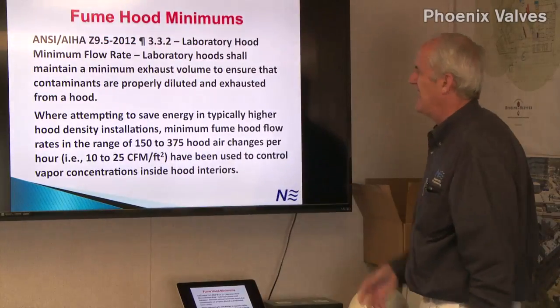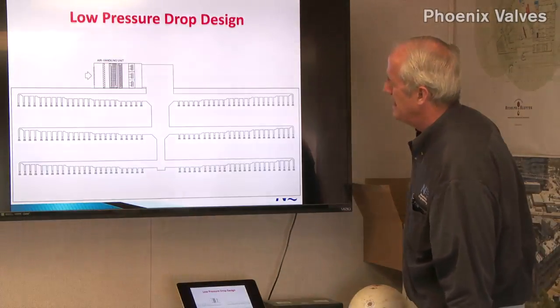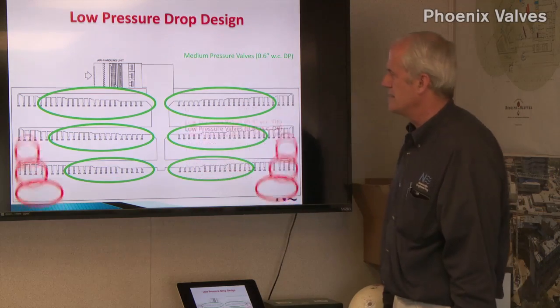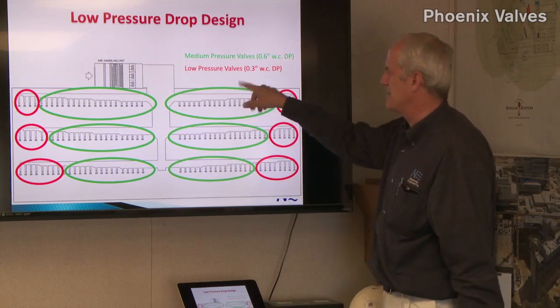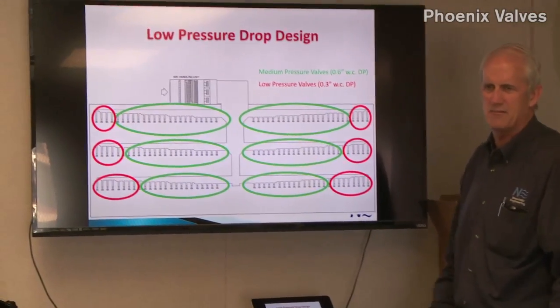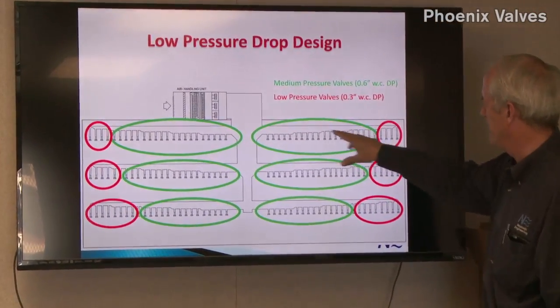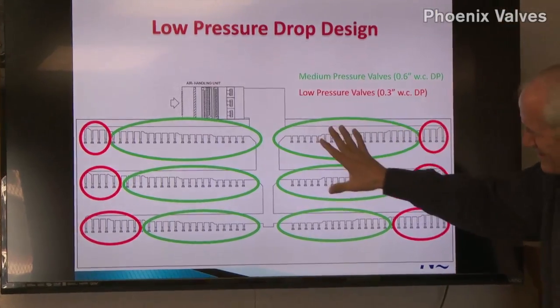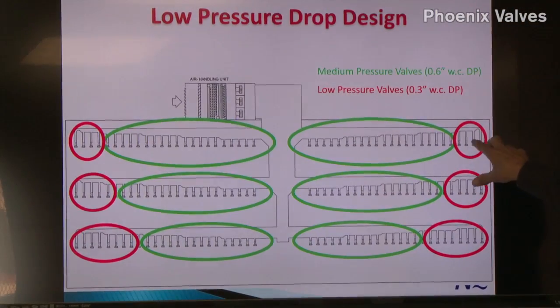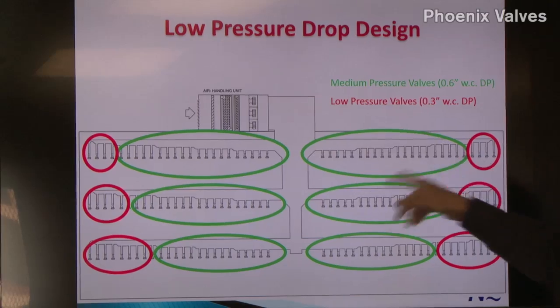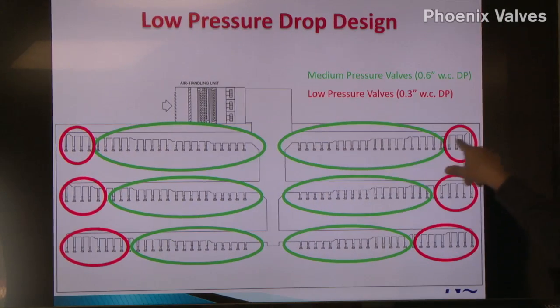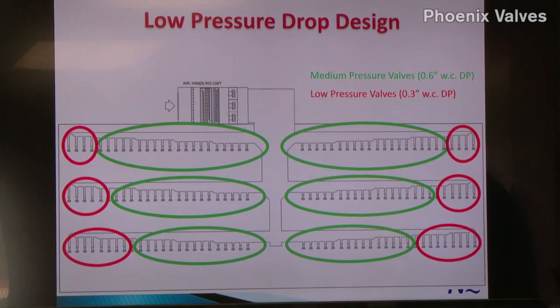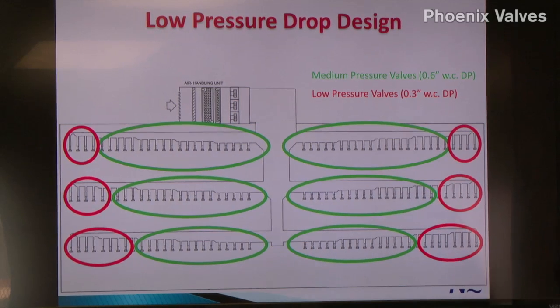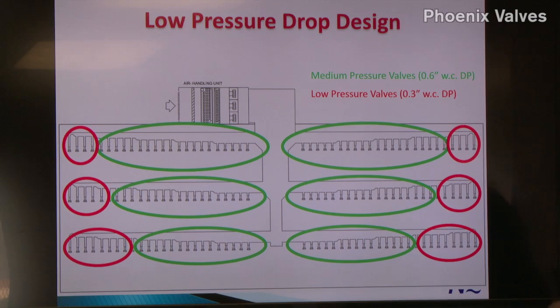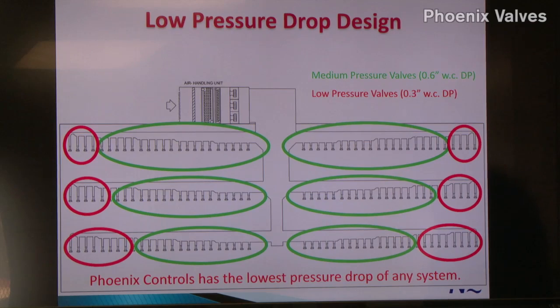Okay, we do tracking control. Just in terms of the way the building works, right now you've probably got your static pressure set point two thirds of the way down your branches, something like that. One thing we sometimes recommend is maybe measuring out here, and if you have plenty out here, as it moves around, you can reset your static set point based on some settings out at the fingertips. With not being done on this building, probably not needed for a vivarium, but some of your science buildings, it's something you could look at.